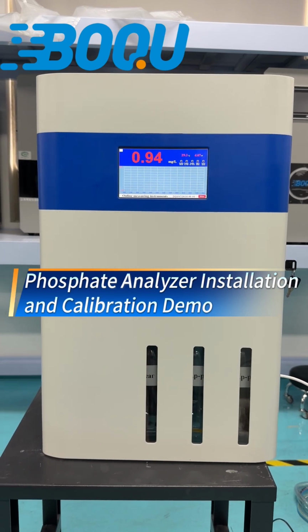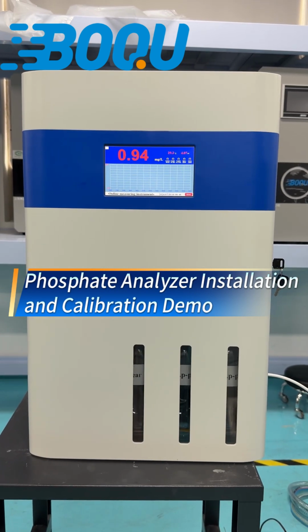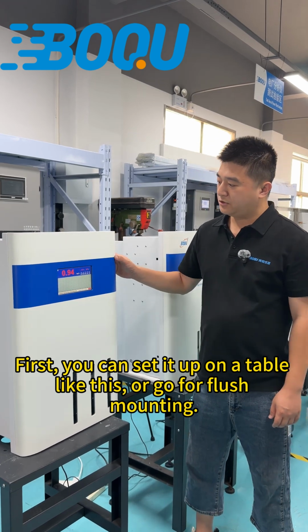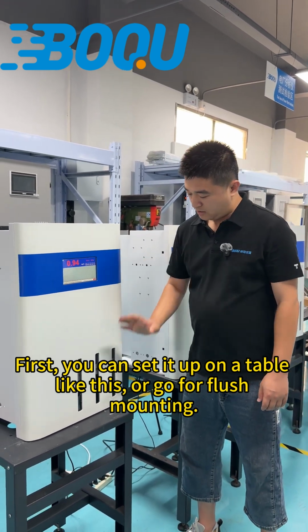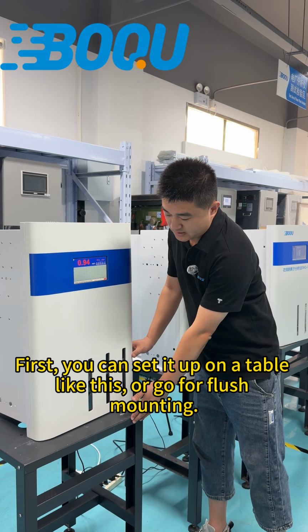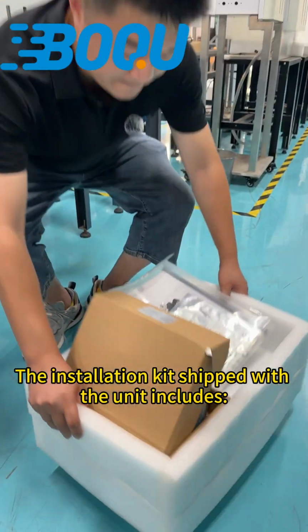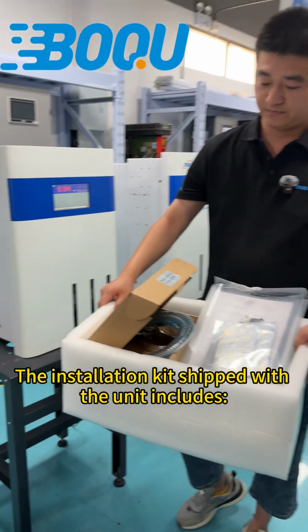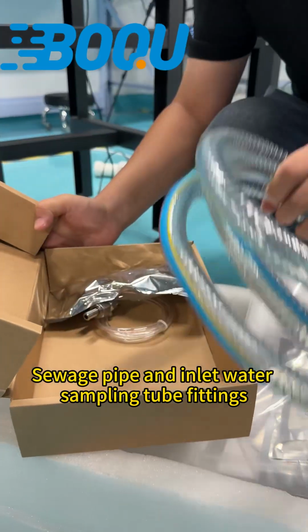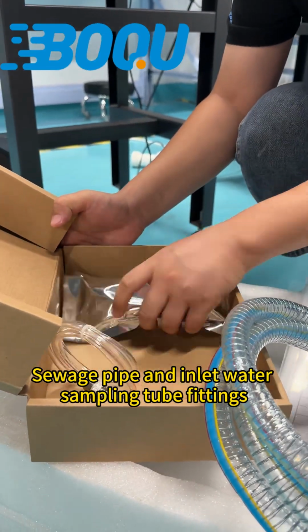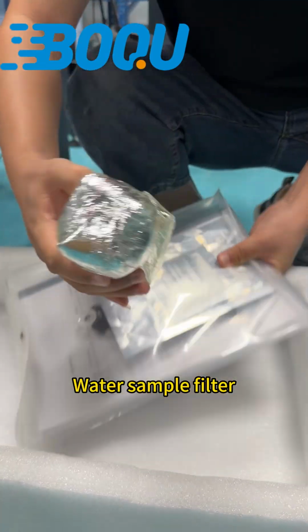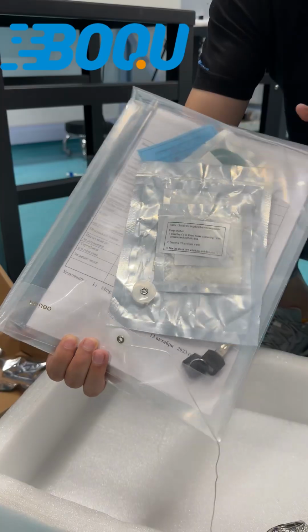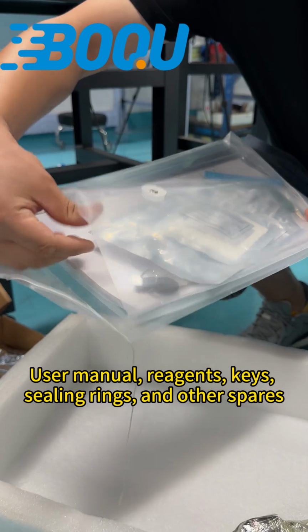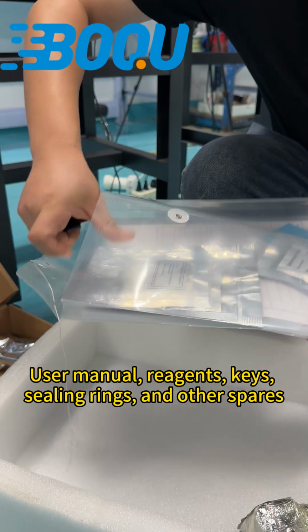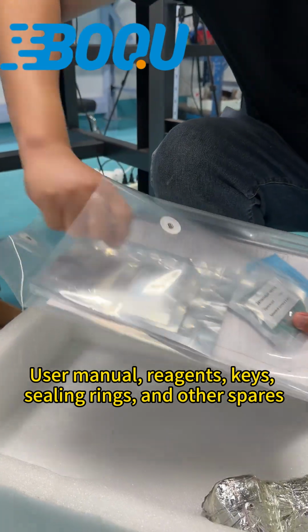Phosphate analyzer installation and calibration demo. First, you can set it up on a table like this, or go for flush mounting. The installation kit shipped with the unit includes sewage pipe and inlet water sampling tube fittings, water sample filter, user manual, reagents, keys, sealing rings, and other spares.